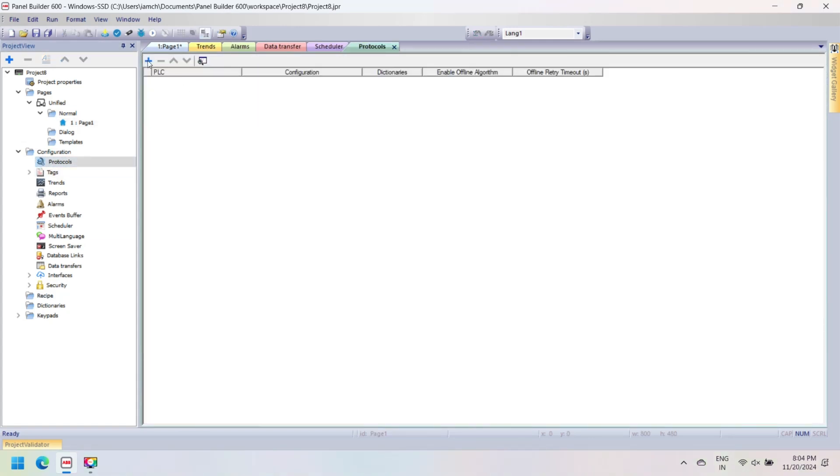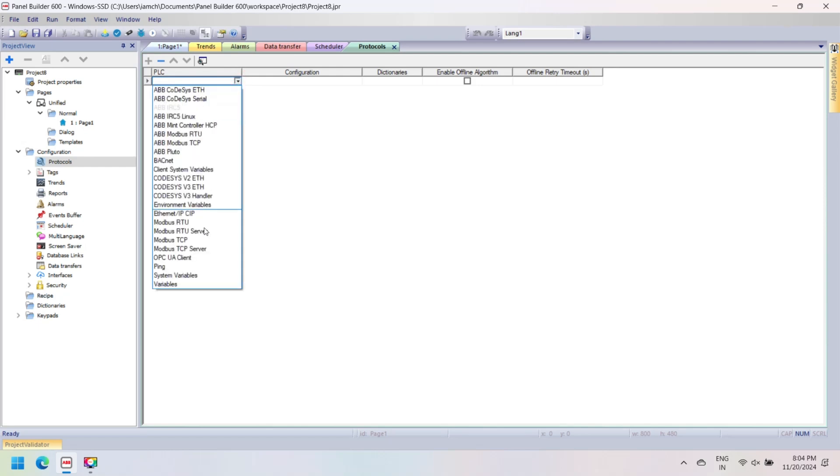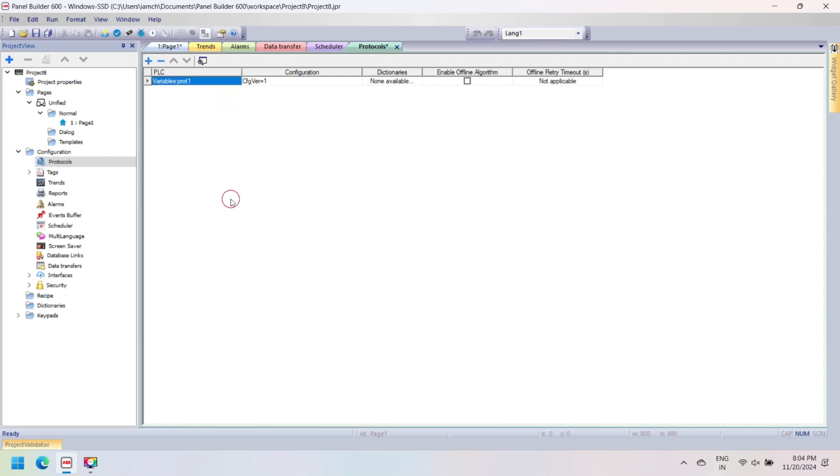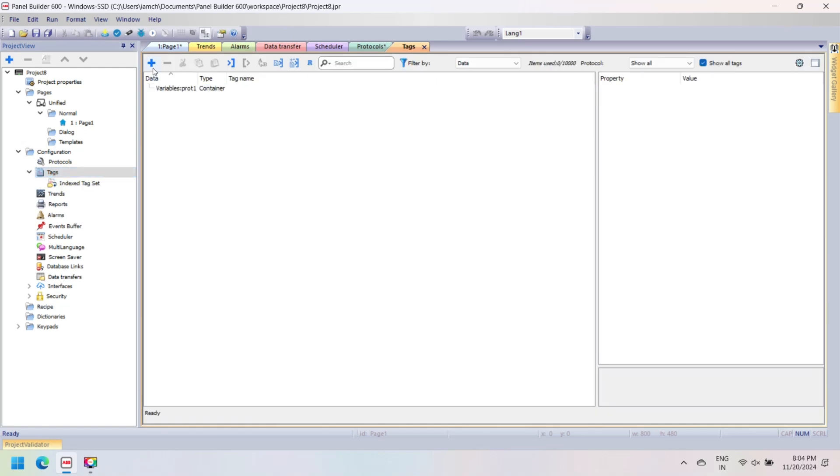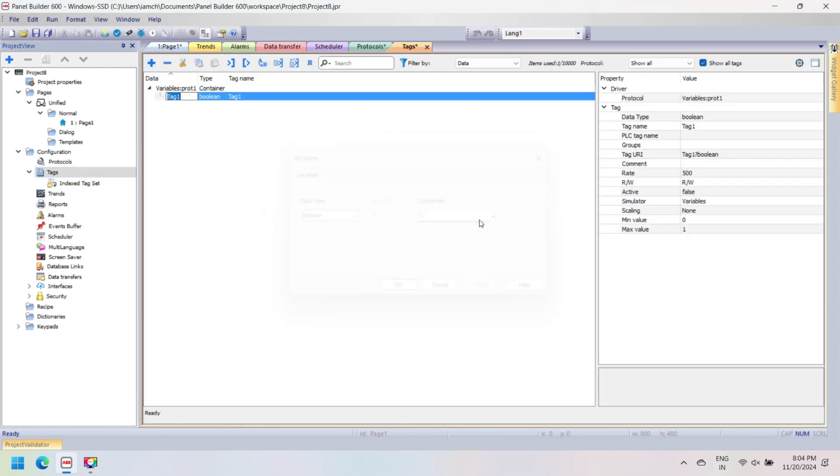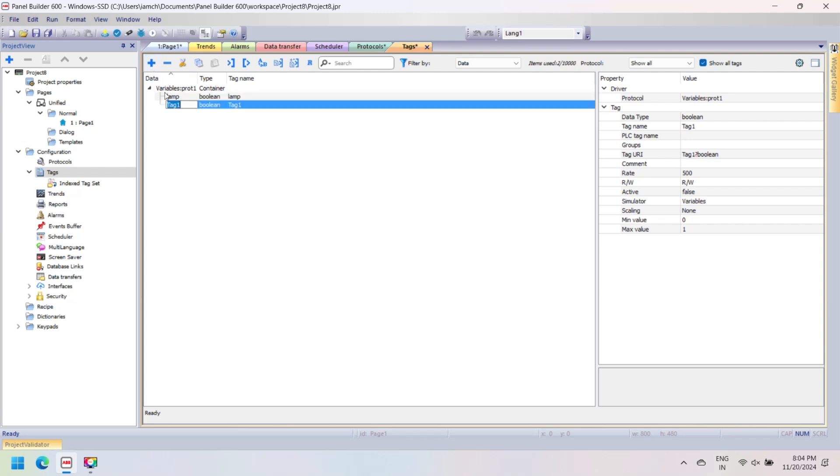Define communication in ABB Panel Builder. Communication configuration is defined for communication between PLC and HMI. ABB Panel Builder supports protocols like Modbus TCP/IP, Modbus RTU, Ethernet/IP, etc. Device communication drivers are configured in the protocol editor. You can add up to the maximum number of protocols.